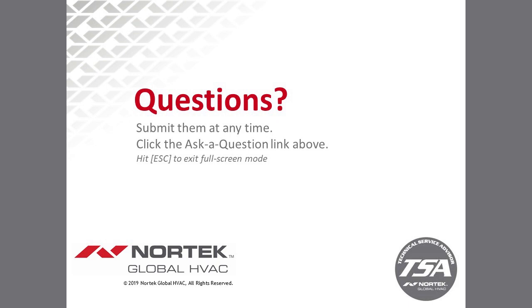So the first question that we have here is, can the furnace prime itself after a shutdown? Basically on that, what you want to make sure is that all the traps that would leave the furnace are primed. On some of the smaller BTU furnaces, you can get away with not priming the trap. What'll end up happening is that through the first run cycle, water will collect in the collector box, and then as soon as the inducer shuts down, water will then drain into your main drain and will then automatically prime your trap.